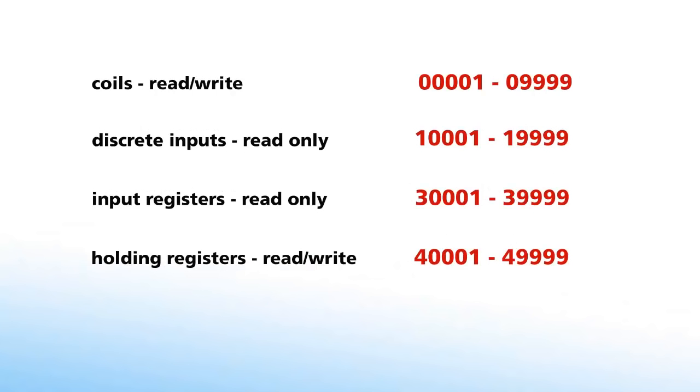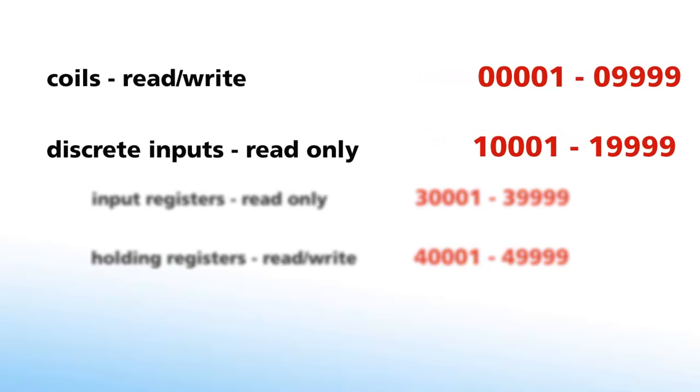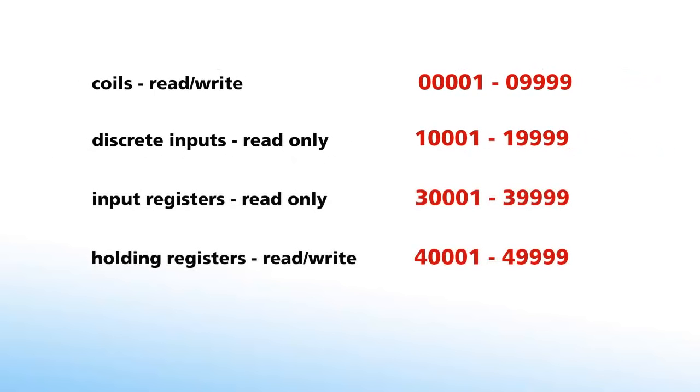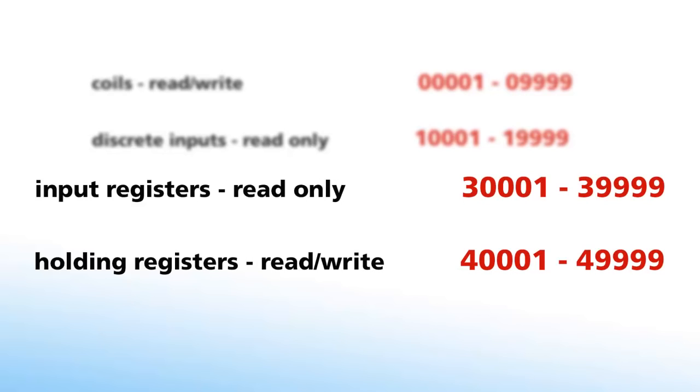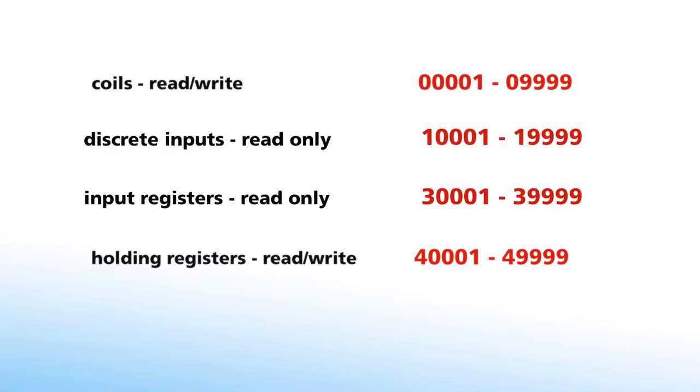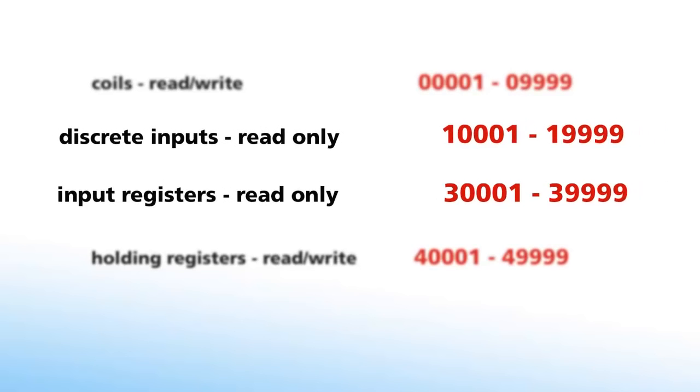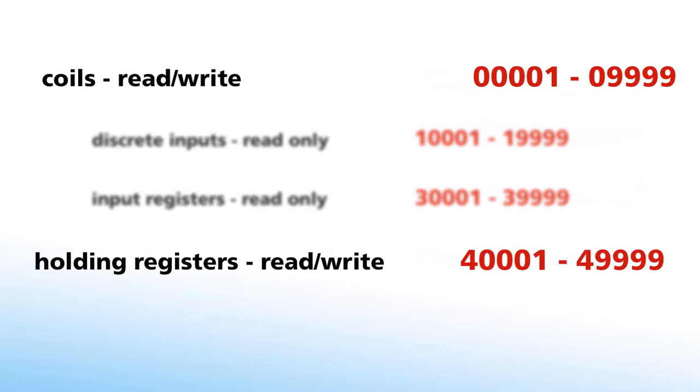Now let's talk about Modbus' eccentric addressing system and the different data tables. There are four tables where information is stored. Two tables store simple discrete values called coils and two store numerical 16-bit values known as registers. For each type of data, there is one read-only table and one read-write table.